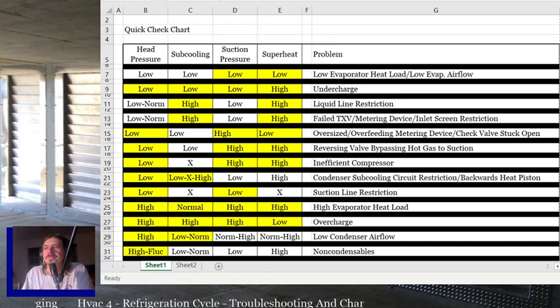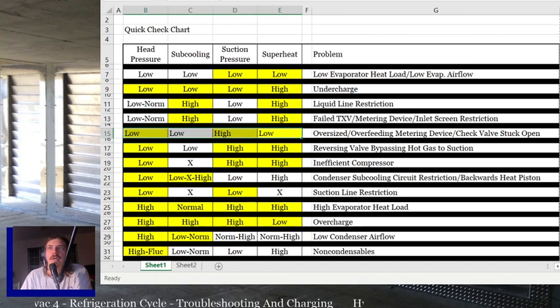So what I have here is, again, head pressure, subcooling, suction pressure, superheat, what they are, then what the problem is. If it's highlighted in yellow, that means those values together help you determine what the issue is. So basically, let's start with the first one real quick, right? The reason suction pressure and superheat low is in yellow is because, guarantee you, look through this whole line. Do you see anywhere else where suction pressure and superheat is low? There's nowhere in this chart where suction pressure and superheat is also low. Okay? So that means if you see low suction pressure and low superheat, that is 100% every time, I don't care what you say, low evaporator heat load.